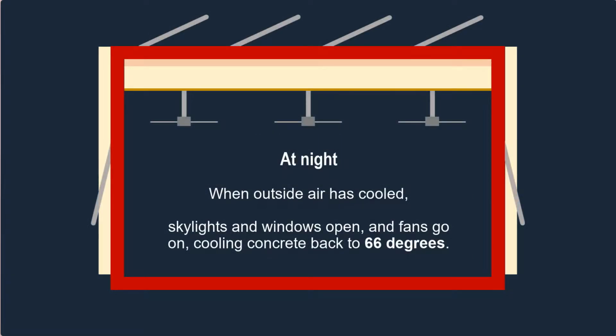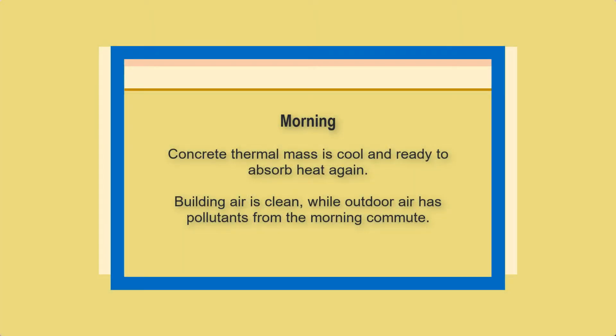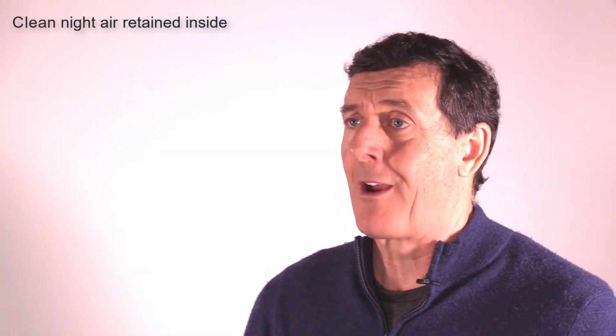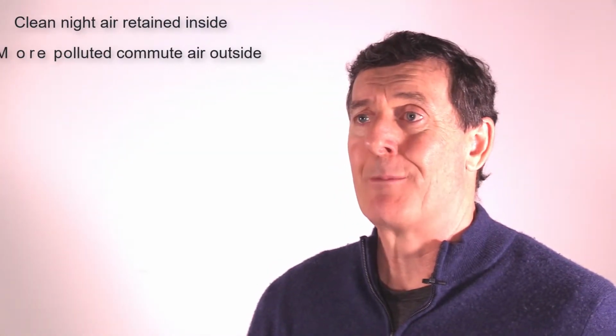In the middle of the night, when the temperature has dropped, the building management system tells the windows and skylights to open, the fans go on, and we cool that concrete back down to about 66 degrees, exchanging the air when it's cleanest outside. So when occupants arrive during the day, the thermal mass is ready to absorb heat again, and the air quality is actually better inside the building than outside, because we've got early morning air inside and commute air outside.